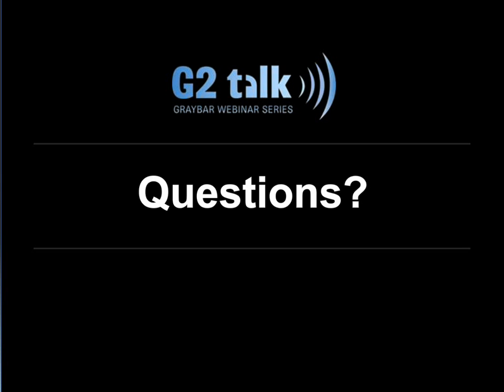Dave, first question. Can we use this device for medium voltage applications? Very good question. At this point, TeSys T can be used up to 830 volts is what it can detect. It's UL listed at 600 volts only. And so Schneider does have something called a Sepam relay that we can use for medium voltage applications. It's similar to this. But typically this is a low voltage device. And if you need it to be UL listed, 600 volts and under is where it needs to be. Thank you, David.